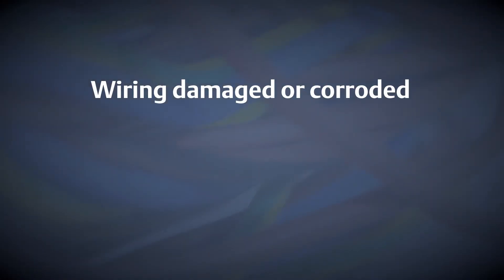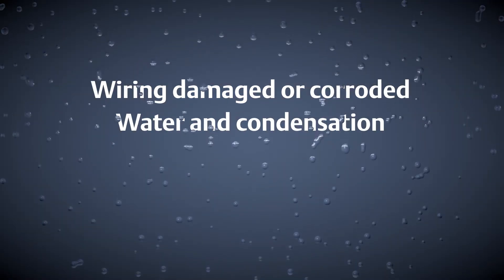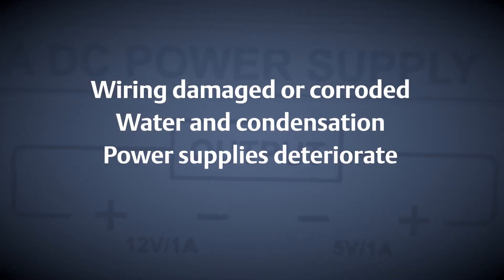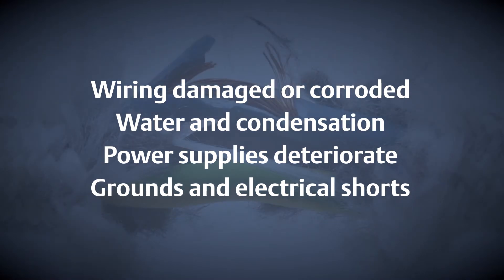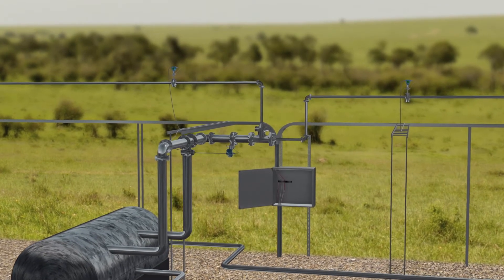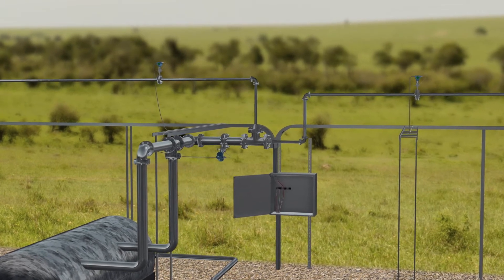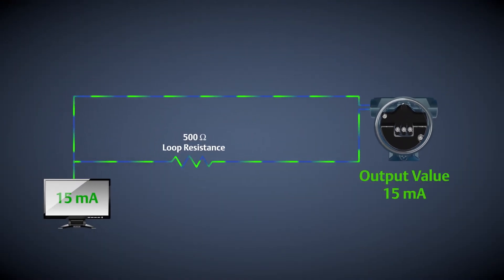What are some of these risks? Wires can become damaged or corroded. Water and condensation can find their way into housings and conduit. Power supplies can deteriorate and become unstable. Grounds and electrical shorts can inadvertently be introduced to the loop. All of these issues can impact the integrity of your 4 to 20 milliamp loop, causing the control room to receive inaccurate measurements and potentially lead to dangerous on-scale failures.